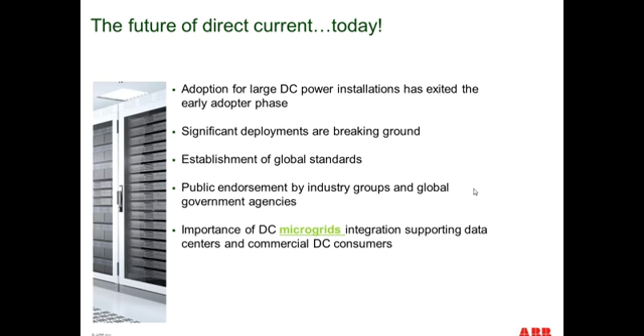We advocate focusing on the hyperscale data center and large user side, looking at bulk replacements or migrations of servers. We recommend targeting a 500 kW or 1 megawatt type of load. As with any technology refresh, you usually take a good portion of the data center out of commission or build elsewhere and migrate over. I don't think it's practical to retrofit servers already in a rack, since you'd have to replace the power strips, cords, and feeders. So you're well into a major infrastructure project going that route. Integrating DC as part of a technology refresh may be a more cost-effective approach.